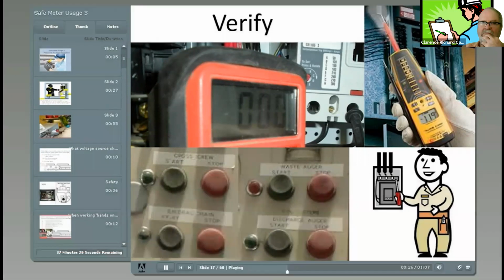Necessary for your application. This step is most important and often overlooked. It may not be necessary or prudent to check if the voltage has been disconnected at the electrical breaker when verifying if the equipment is now rendered inoperable by checking with a test meter. In some cases where the mechanical equipment is being serviced and the electrical circuit is not being worked on, verification of the equipment inoperability may be accomplished by trying to start the equipment after it has been electrically locked out.